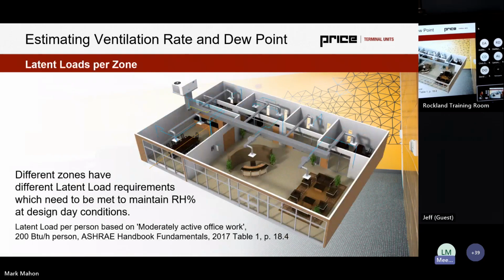Well, we also have different latent load requirements in the same way we had different sensible load requirements for the zone as well. And this is what we need to maintain typically about 50% relative humidity on design day. So that's where that 75-62 dry bulb, wet bulb temperature comes from that we often see kind of assumed within engineering design. That is 75 degrees as a design day temperature with 50% relative humidity.